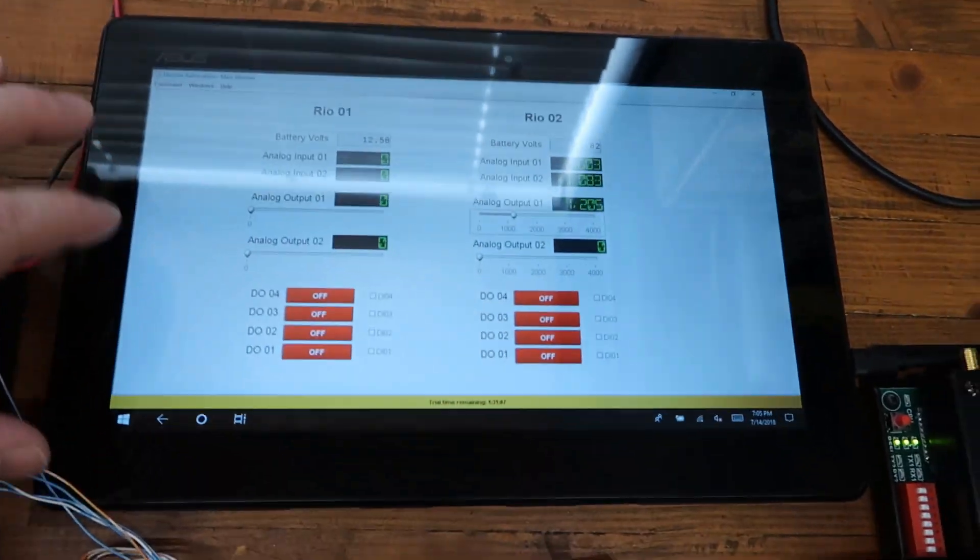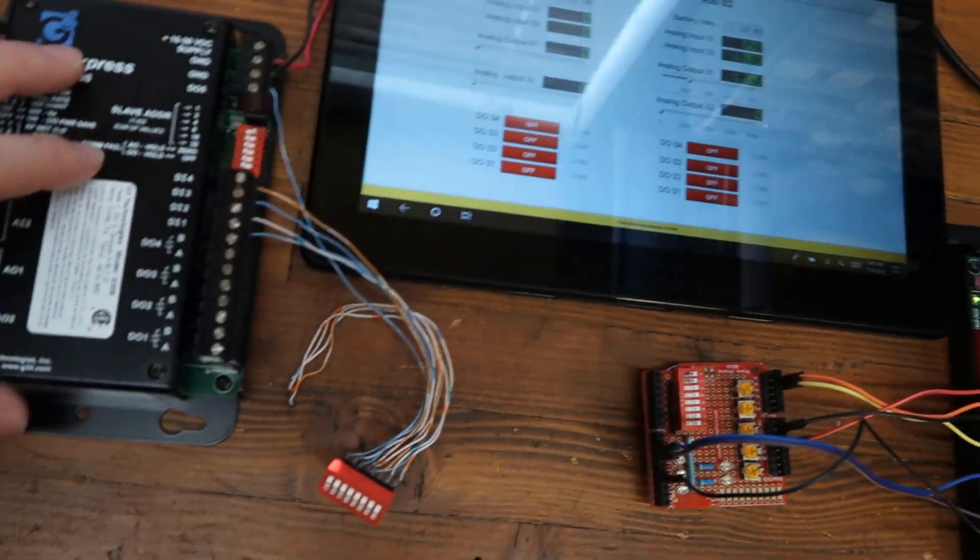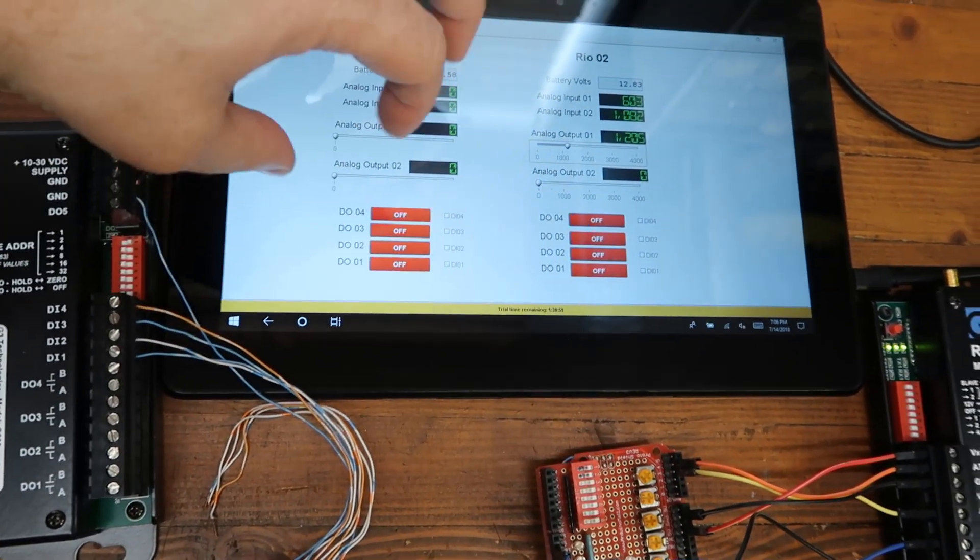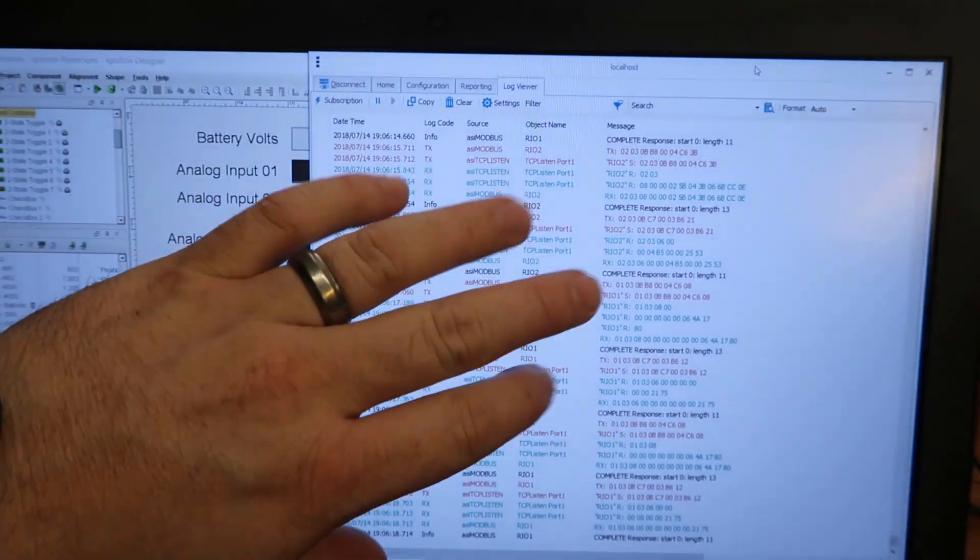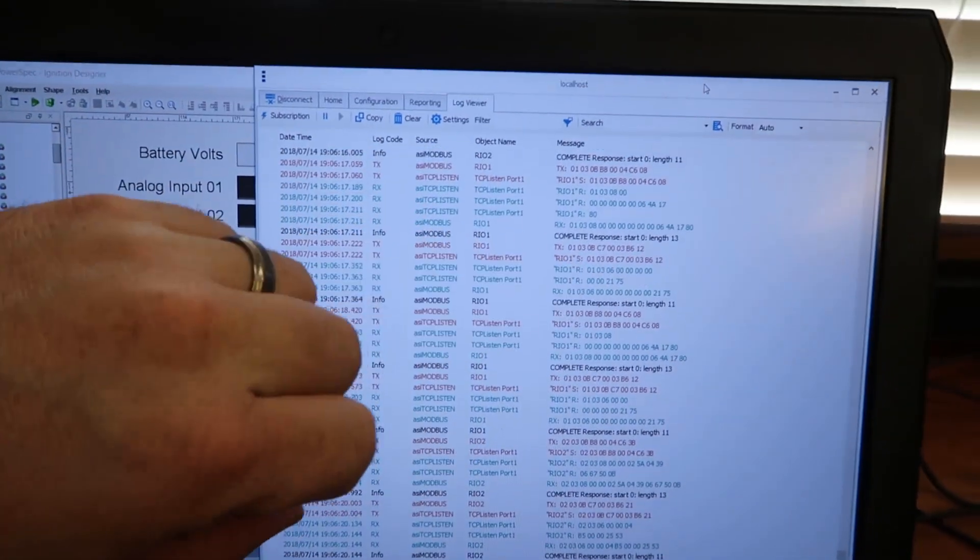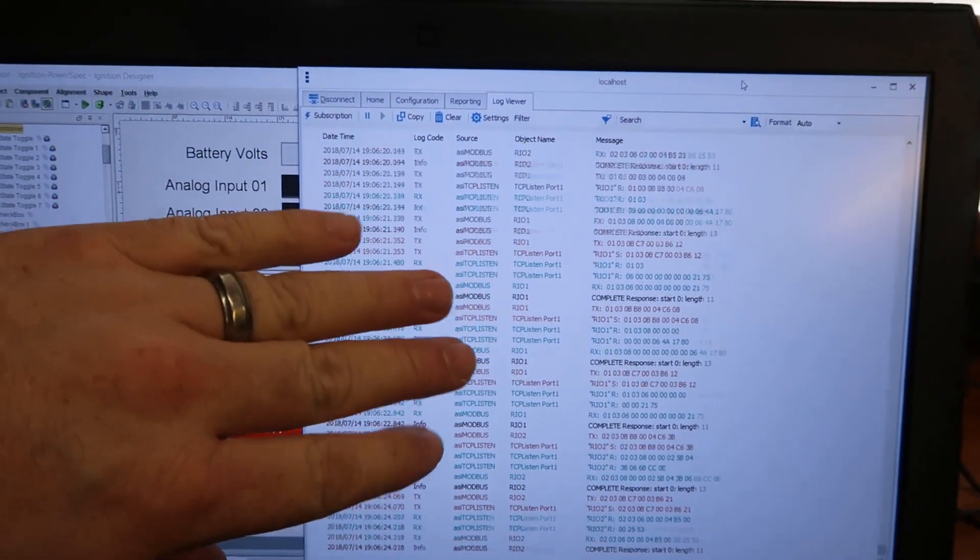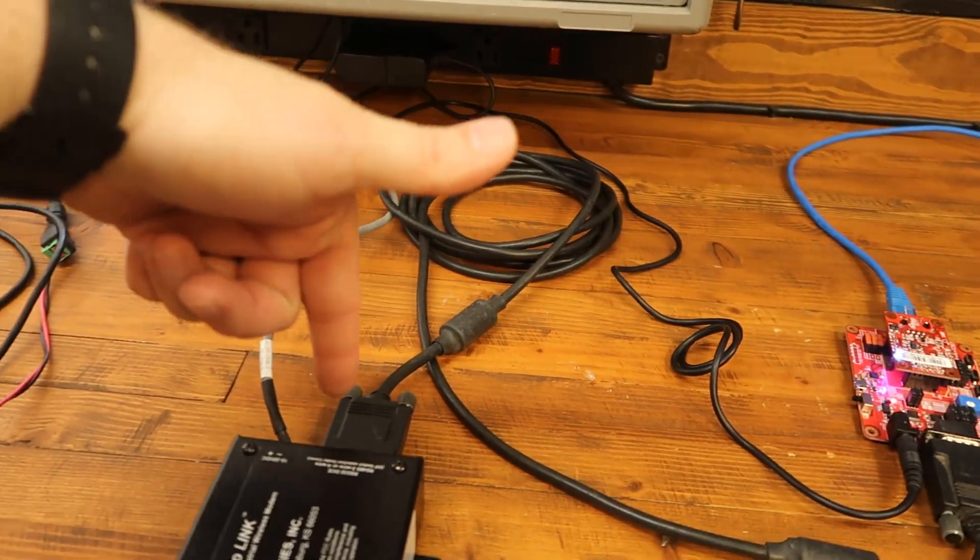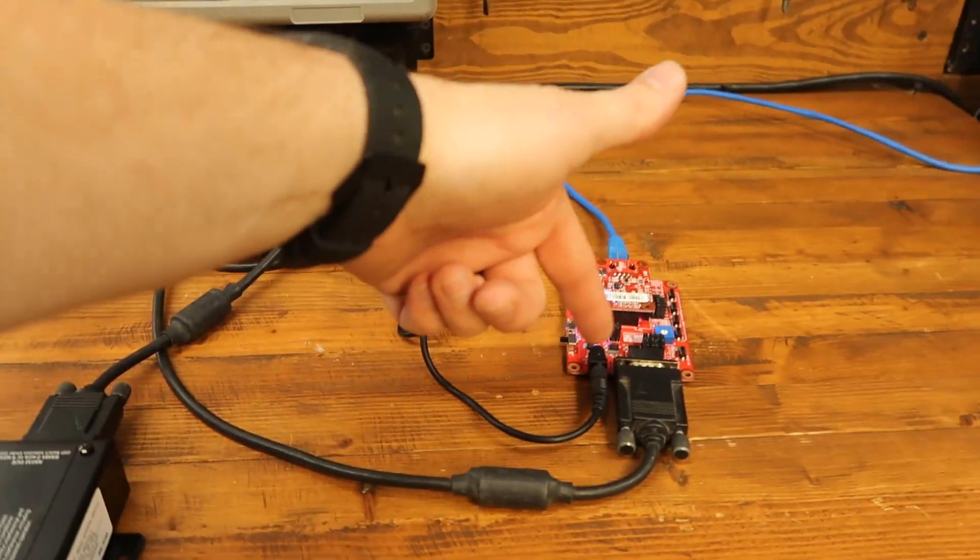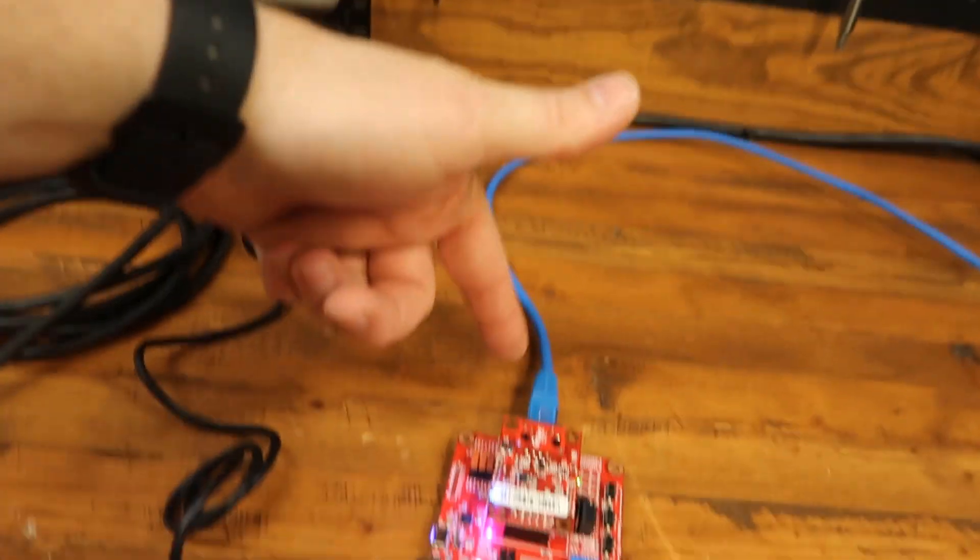I'm using Ignition and ACM because these are Modbus devices. So Ignition is the SCADA host. And ACM is a polling engine that can communicate Modbus RTU. It can also communicate Modbus RTU over TCP IP, which is what happens when no longer is it Modbus RTU to a serial port. It's Modbus RTU over TCP IP.